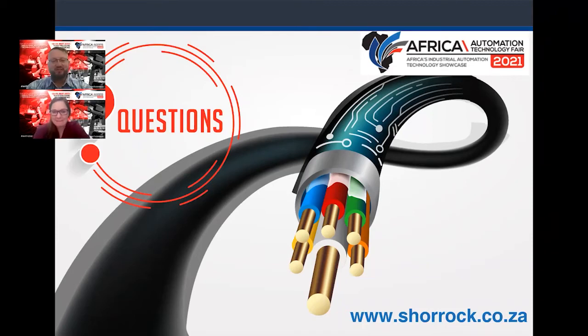Okay, so like I mentioned, we can offer it with Modbus RTU and IO-Link. So those are the two communication protocols that are currently available, but we're hoping later in the year to also have Modbus TCP available, hopefully before the end of the year. Great, thanks. Can I series and parallel these PSUs? Yes, you can. So for applications where you require a 48 volt DC application, you can series these two power supplies. The key to seriesing two power supplies is it's really important to then switch both on at the same time. But it is possible for applications where you require this.